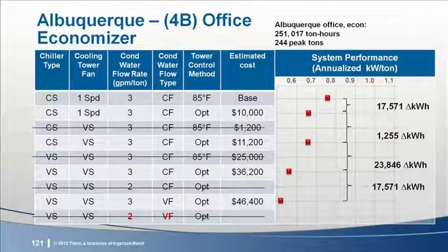The problem is that economizers and a milder climate take out many of the hours when the system is most efficient. The payback on our investments may simply not be favorable enough, and we may want to look for a less costly alternative or wait until we need to replace the chiller. The key is to identify the right opportunities, then compute rather than assume the returns on potential investments.